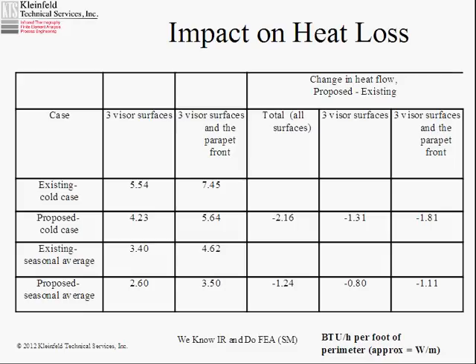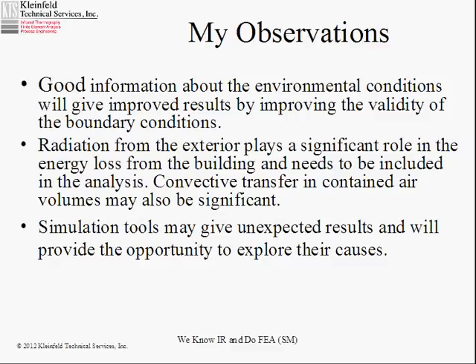The impact on heat loss for the existing design: for the three visor surfaces — top, front, and bottom — drops from 5.54 to 4.23 in the proposed. If we include the front of the parapet, the number goes up but still represents a significant drop. For all surfaces of the entire model, heat loss drops by approximately 2 versus 1.3 or 1.8 for the various surfaces. You don't see as big a loss in the seasonal case because the conditions are milder.